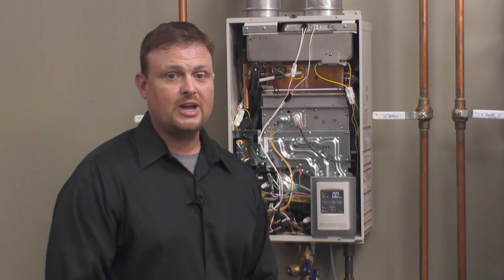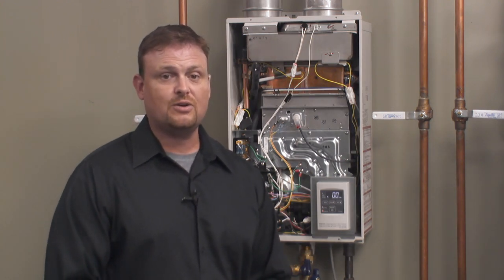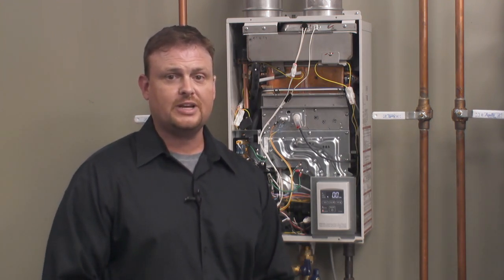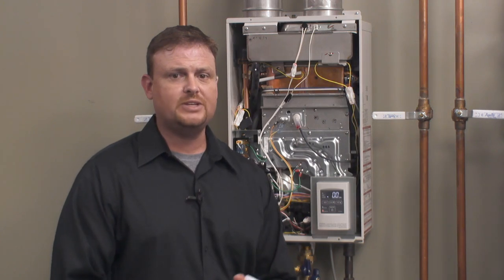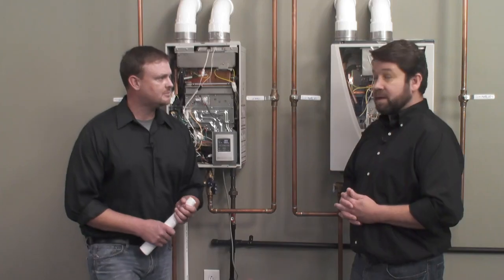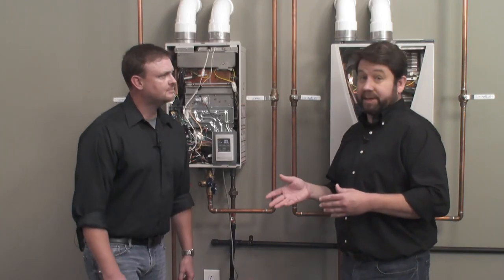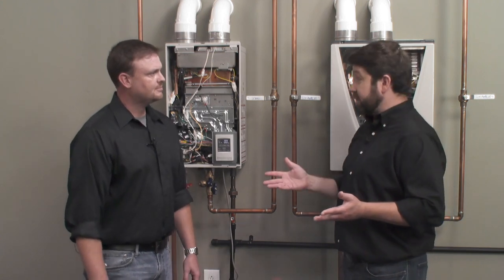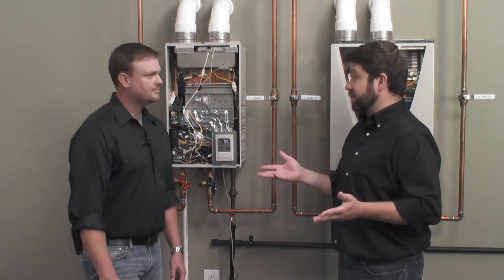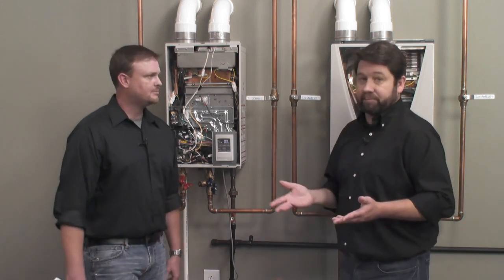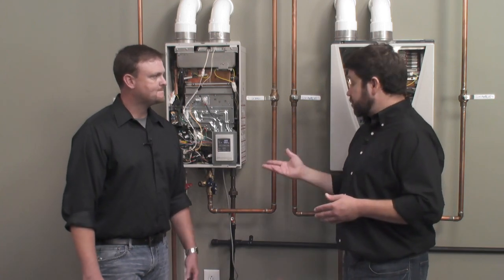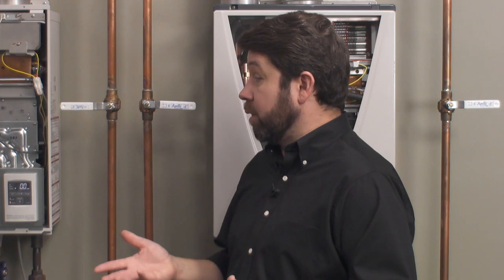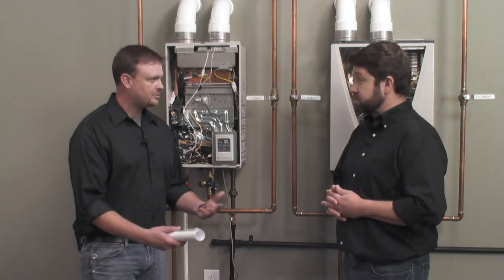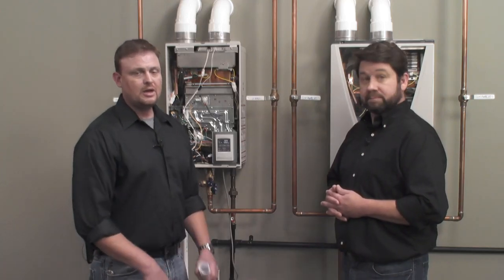All right, it looks like we got a couple questions already. So the second one there is, can you only drain into a PVC drain, not metal? It doesn't have to necessarily be PVC, but it cannot be metal for the condensate because of the acidic nature, unless it were a stainless steel drain, which prices it out of range. But you could use silicone tubing or any other material that's going to be appropriate for condensate. Right, and also you always adhere to your local codes, whatever they're telling you, you cannot do, then adhere to that.